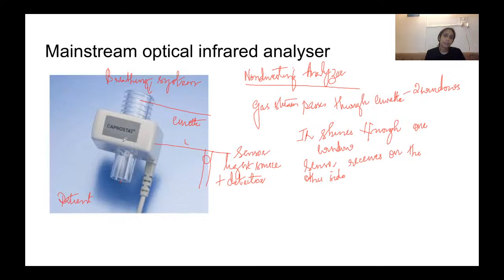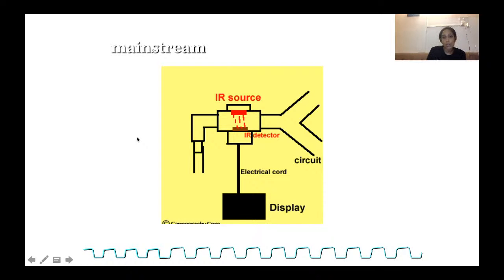So the light source is here, the detector is also here. The light passes through three ports, then goes through a filter which corrects it to a particular wavelength, and then displays it. This is your mainstream, this is the infrared source, this is the infrared detector, and this is your display. This is from the patient, and this is going to the machine end. These two Y ports go to the machine, and the sensor will be kept here.